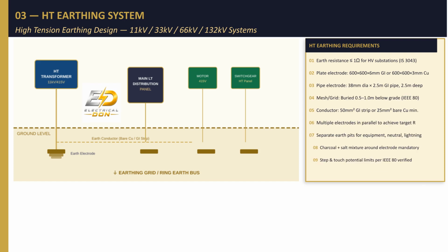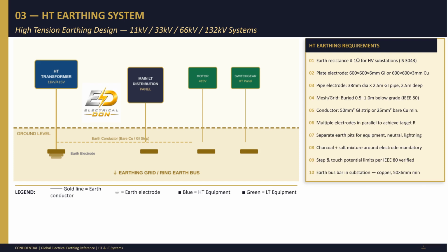HT earthing design focuses on robust earth grids. Key requirements include an earth resistance of 1 ohm or less for substations, use of plate or pipe electrodes, and meeting step and touch potential limits per IEEE 80. Separate earth pits are mandatory for equipment, neutral, and lightning protection.